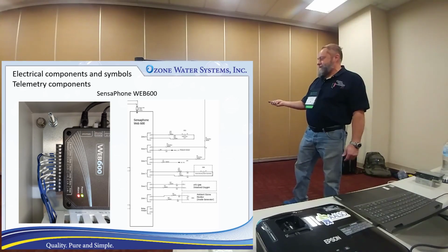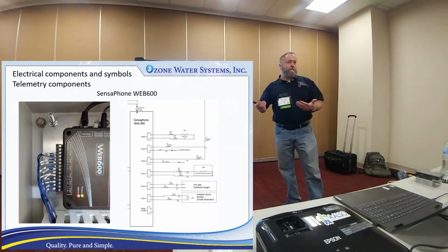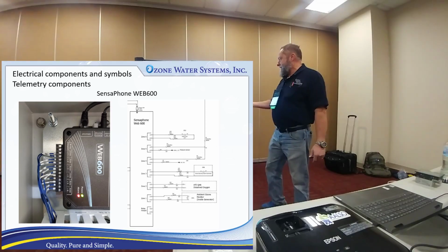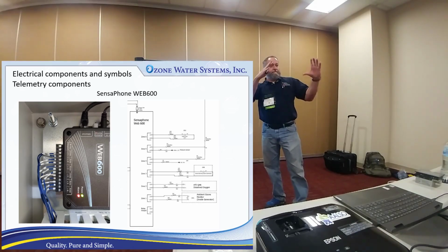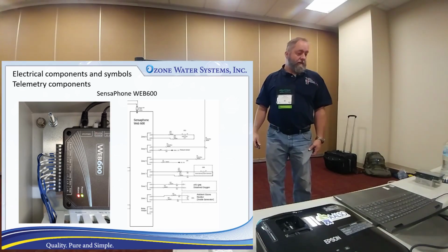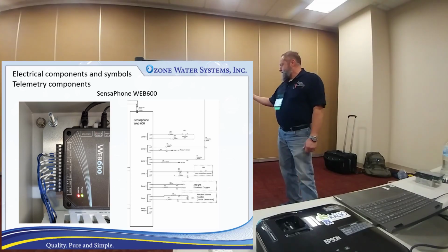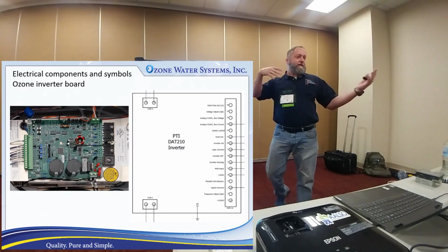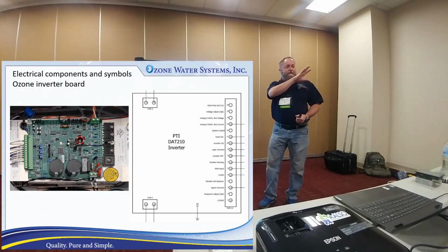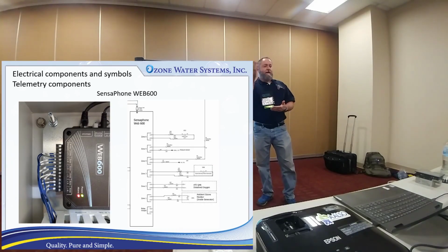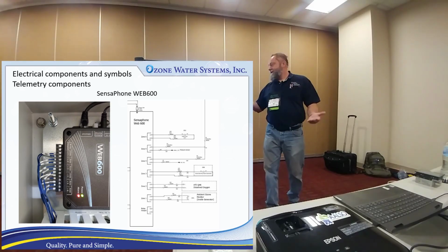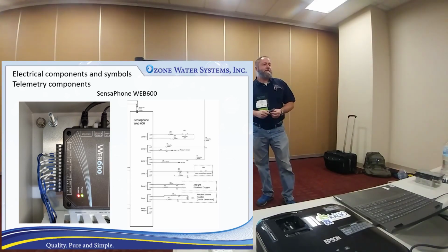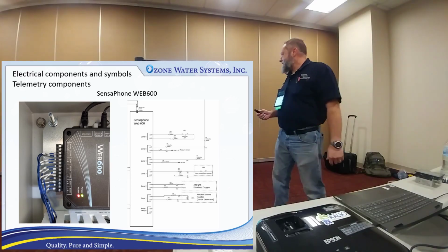But anyway, each of these outputs, you can make it an analog signal or a relay signal. You can hook up temperature probes to it. And then within the programming for that, you can set up, if anybody saw the demo up top, we pulled up the little graphic on the computer to show you what it looks like, but pretty neat. The other thing you can do is, if you've got different technicians on call at different times, you can pre-program in there who's on call at what time, so you can have different emails. It'll send it out to this guy on the weekends, or you're on call at night, or during the week, it might be you. You can have it automatically divert the messages to the right person at whatever time you want. So it's a pretty neat little device.